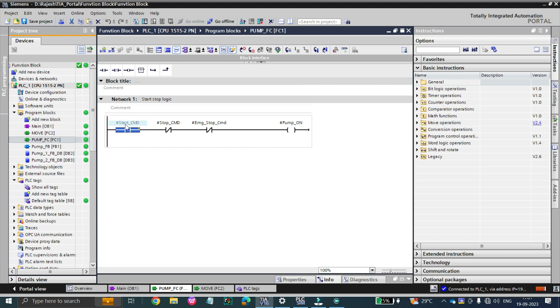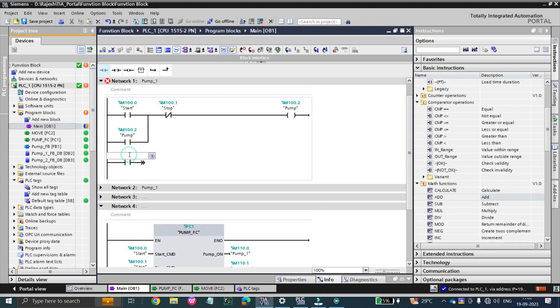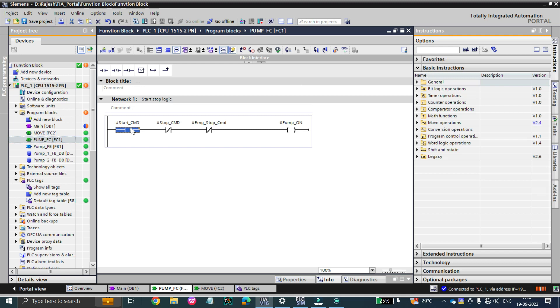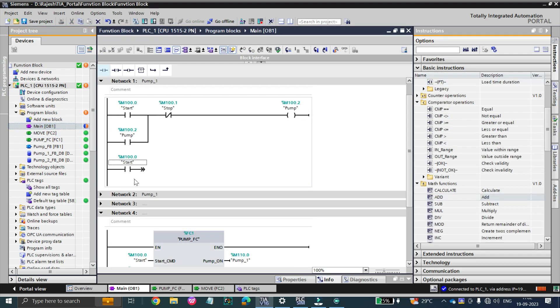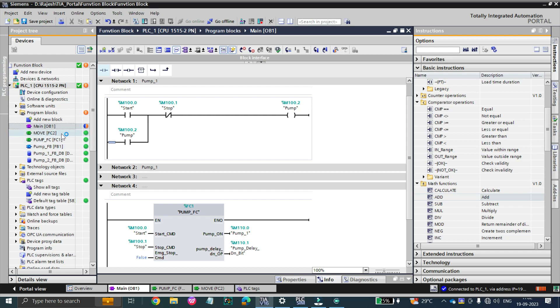Likewise, in main we use M100.0, and in pump FC we can also use M100.0 — but a local tag like 'start command' can't be used in the main block. When you type 'start' in the main block it searches for something else — you can't access a local tag globally. The global can be called in any function block or function. These are the basic differences between function and function block. In the next video I'll show how to use function, function block, and OB — organization block — and the complete concluded difference. See you in the next video, thank you.